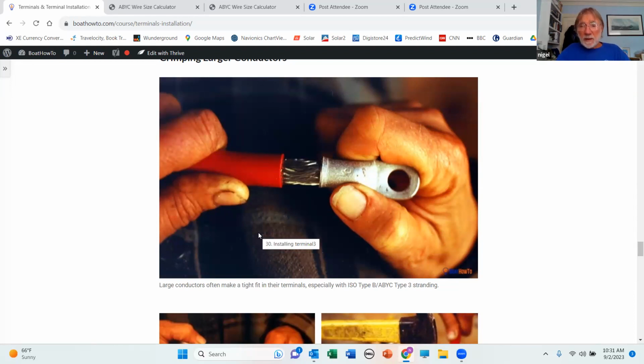It's not against standards. It doesn't break the rules to take two conductors and shove them into a larger terminal and then crimp on them. However, if you think about the logic of that, you've got a round hole, you're putting two round things into it. There's no way you can get a tight fit in there before you crimp on it. So it's an inherently weak way to make a connection. What we should do is just have a single terminal on a single conductor, and if we need more than one conductor to be terminated at the same point, then we need to put in a terminal post so that the individual terminals get bolted together, or a bus bar, which is a flat metal plate into which you screw bolts or screws, and you can put multiple terminals on the bus bar. When it comes to a terminal post, we're allowed up to 4 conductors, 4 terminals on one terminal post, but if we're going above 4, then we have to use a bus bar and put the multiple conductors on the bus bar.